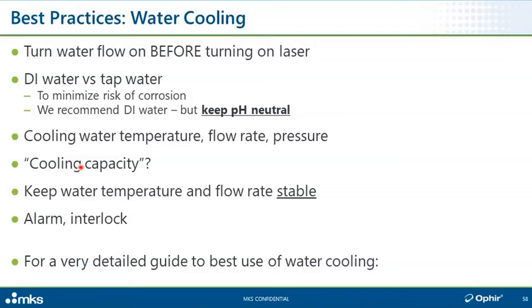But just let's finish the bullets that I have on this slide, and we've got about 1 or 2 minutes left. Cooling water temperature, we have specifications for the temperature range of the cooling water. More in the data sheets, more critical than the actual temperature is the stability of the temperature. Even slight fluctuations in the temperature or the flow rate could be picked up by the sensor and mess up the reading. We often are asked, can we recommend a chiller?